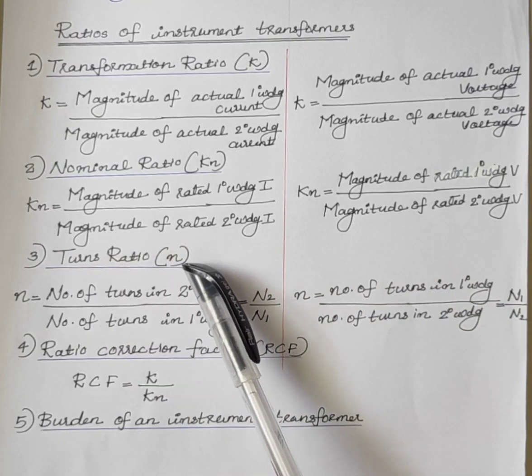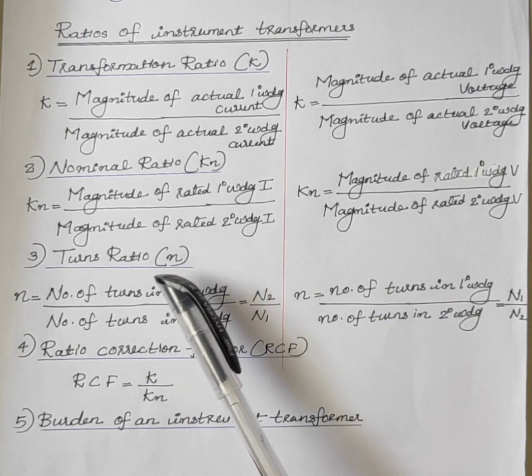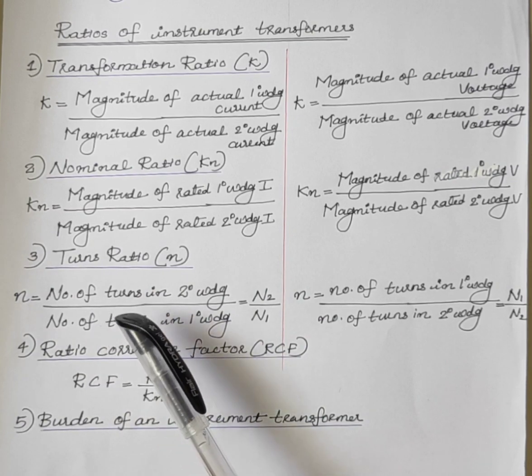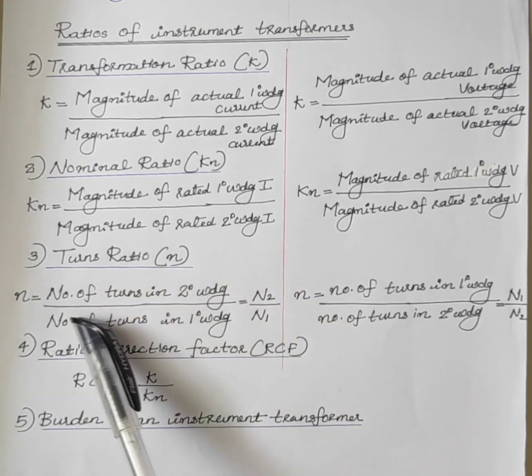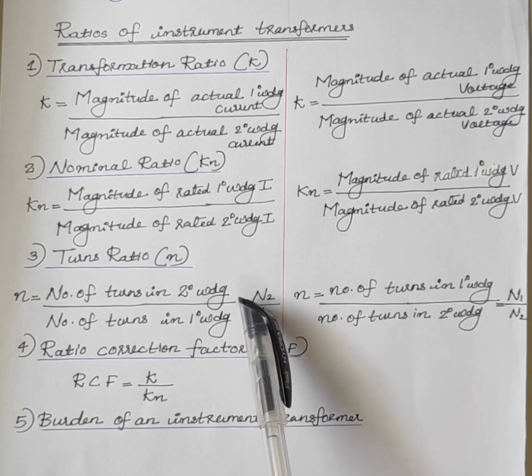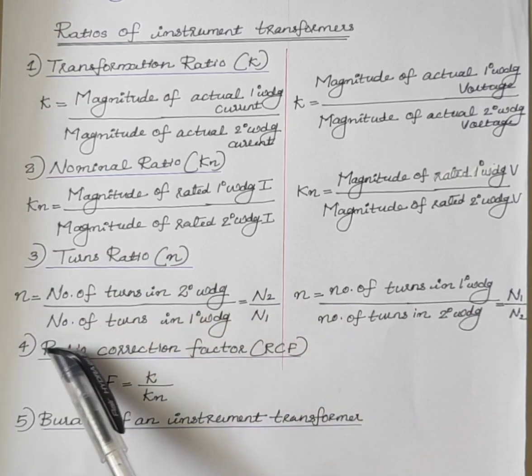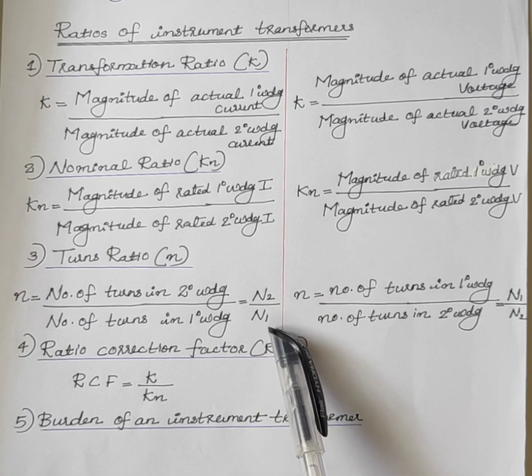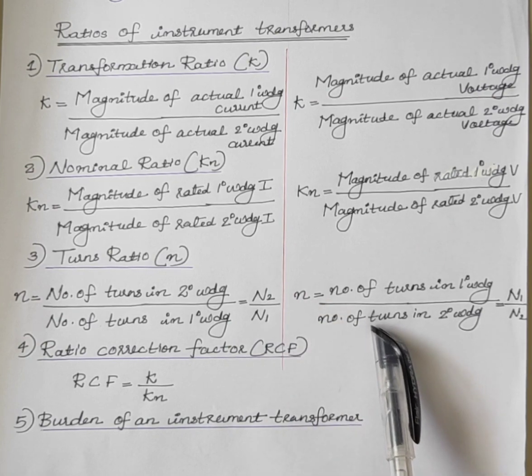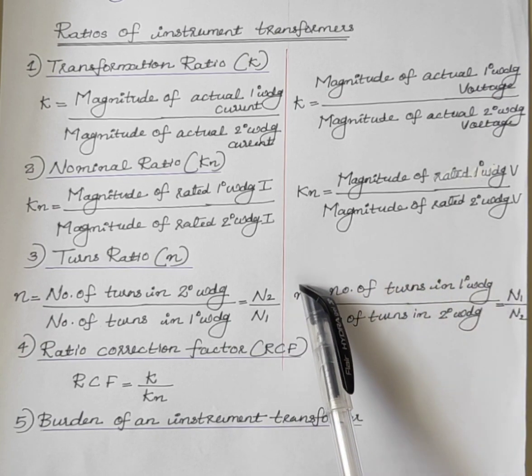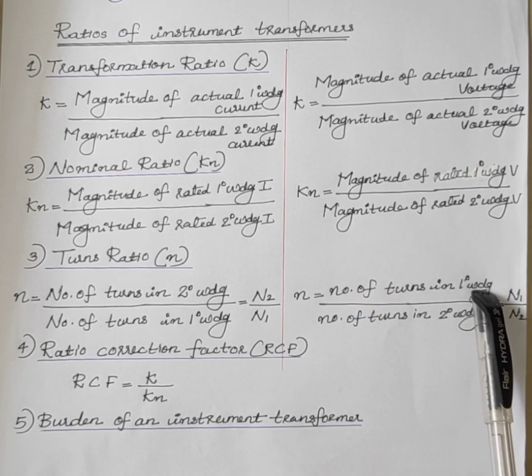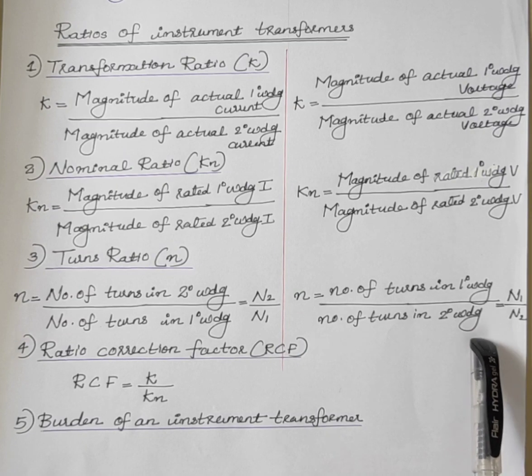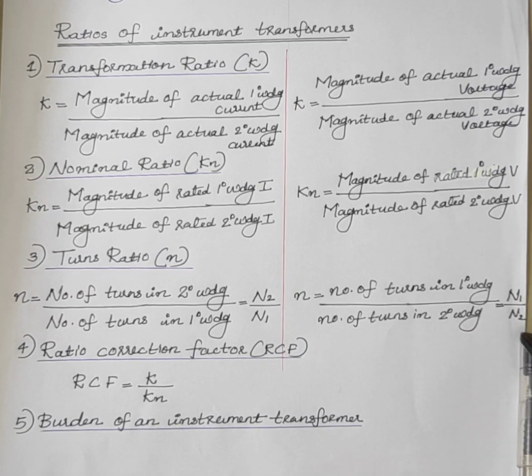The third one is turns ratio, represented by N. The turns ratio of a current transformer is the ratio of the number of turns in the secondary winding to the number of turns in the primary winding, N2 by N1. In the case of a potential transformer, it is the ratio of the number of turns in the primary winding to the number of turns in the secondary winding, N1 by N2.